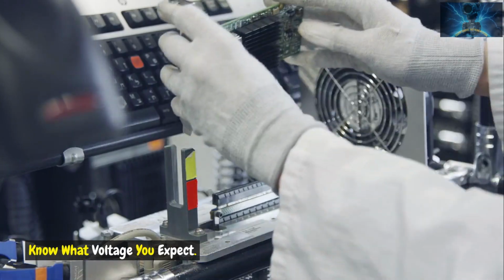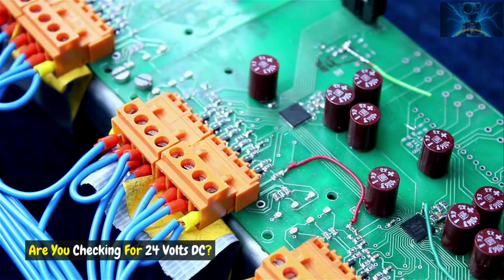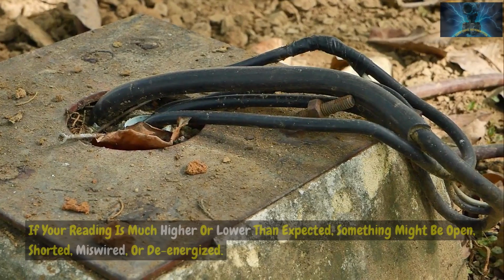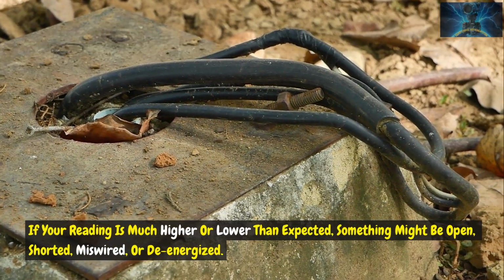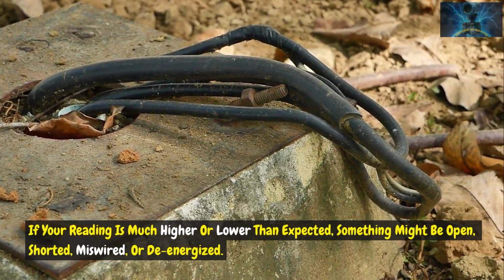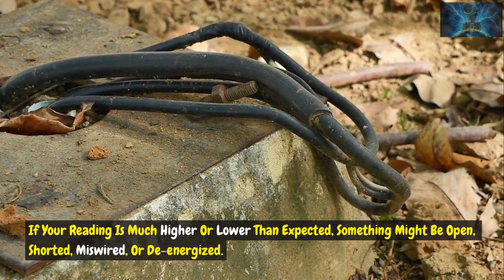Know what voltage you expect. Are you checking for 24 volts DC, 120 volts AC? If your reading is much higher or lower than expected, something might be open, shorted, miswired, or de-energized.